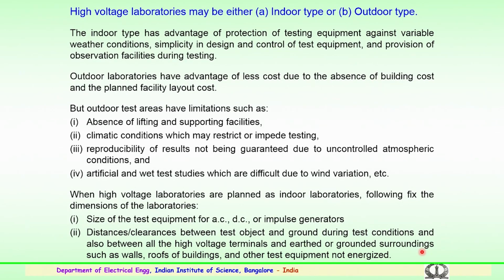So, the high voltage laboratories which we discussed could be of either indoor type or outdoor type. The indoor type facility has the advantage of protection of test equipments against variable weather conditions, the design and control of test equipments are simple, and there will be provision for observation of the facilities during the testing or experimentation which is being conducted. The outdoor facilities or outdoor laboratories have some advantages, like less cost. This could be due to the absence of building cost and the planned facility layout.